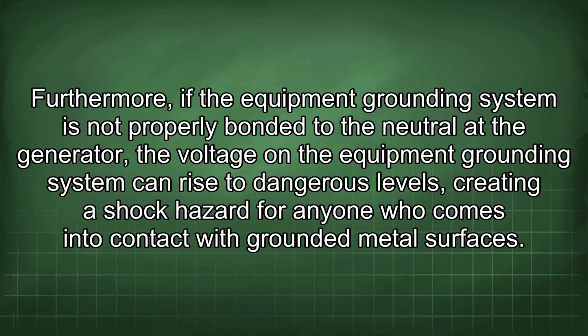Furthermore, if the equipment grounding system is not properly bonded to the neutral at the generator, the voltage in the equipment grounding system can rise to dangerous levels, creating a shock hazard for anyone who comes into contact with grounded metal surfaces.